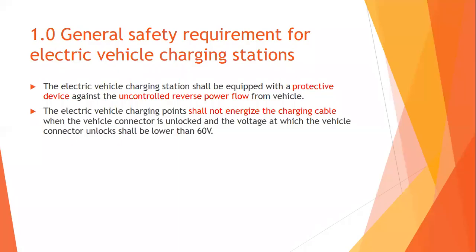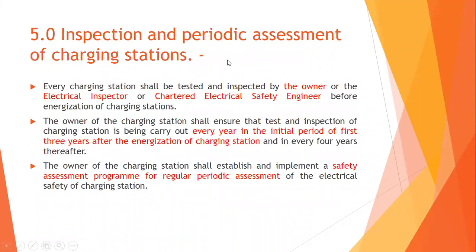Rule 5 covers inspection and periodic assessment. Every charging station shall be tested and inspected by the owner, the electrical inspector, or a chartered electrical safety engineer before energization. The owner shall ensure that testing and inspection is carried out every year in the initial first three years after energization, and every four years thereafter. The owner shall also establish and implement a safety assessment program for regular periodic assessment of electrical safety.